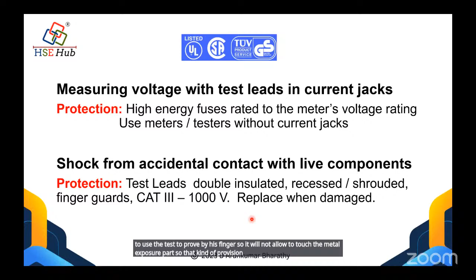But lastly, whatever protection system a certified instrument may have, when it is used above the rated voltage or above the category, then there is no protection. So this point is very important. I repeat again: any test and measuring equipment having all international certification and testing and everything, when it is used above the range or in the wrong category, there is no protection for the user. It may end with arc flash or electric shock. So these are the features of certified instruments.